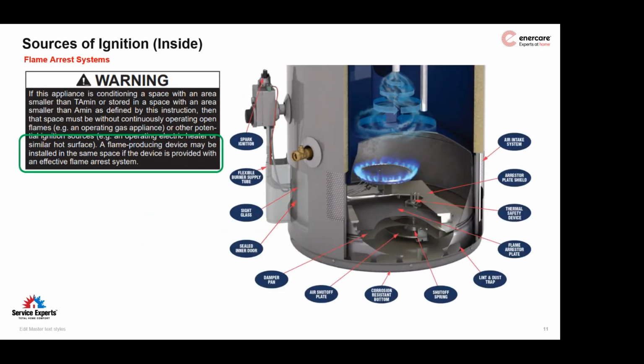Now to that final warning. This is an interesting piece that I think a lot of folks are having a little bit of trouble with, and we're still getting some of this stuff ironed out with Lennox, because we don't like the way a lot of this is written. But because of the way it's written, we have to adhere to it, because currently this is the manufacturer certified instructions. So as I mentioned earlier and highlighted within the warning in green, the mechanical room can no longer have a source of steady flame or spark producing ignition, which includes gas appliances, unless they are equipped with an effective flame arrest device.